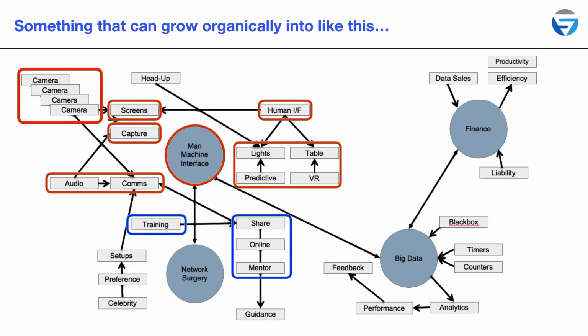But we can start to add more LAN-based services by passing data through the proprietary man-machine gateway. So we can do setups, surgeon preferences, procedure-specific software, for example. We can maybe go online and see if our professor is online, and we can only do that if we start having IP-based services. But we're still squeezing everything through that matrix-based controller if we are matrix, but not if we are IP switch-based.